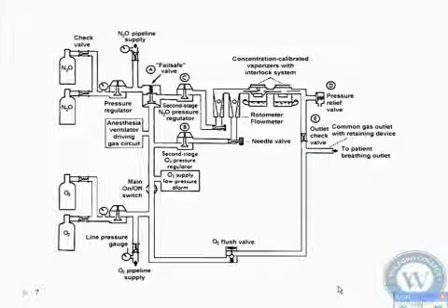Now, that's because you're going from 50 psi down to 26. So there's only one that reduces that. Now, if you were asked, how many pressure regulators are there between nitrous oxide cylinder and the patient? The answer is 2, because you must reduce pressure from 2200 to 50 and then from 50 to 26. Okay? So, is that a little more clear?